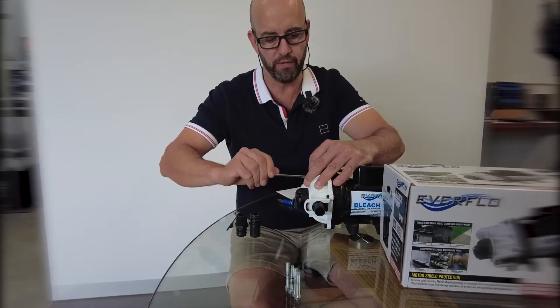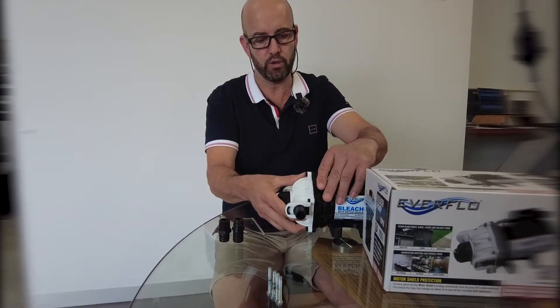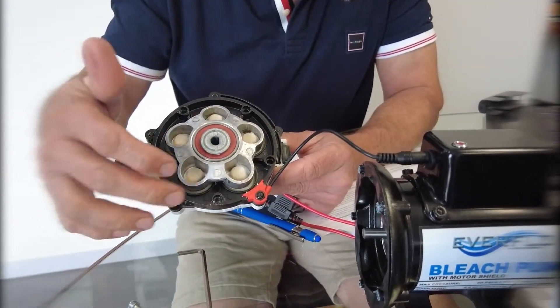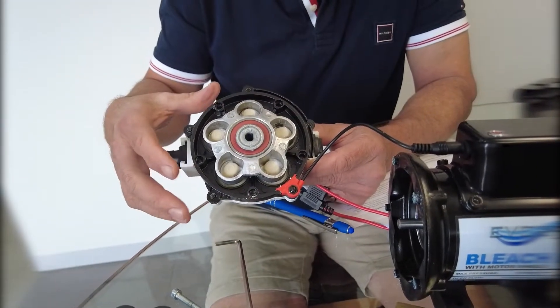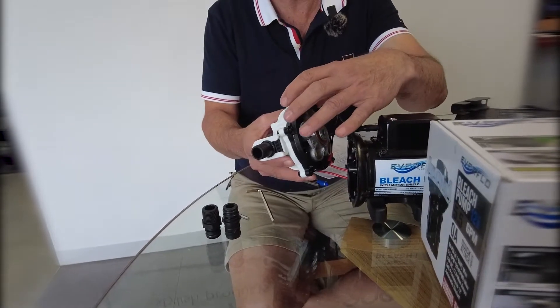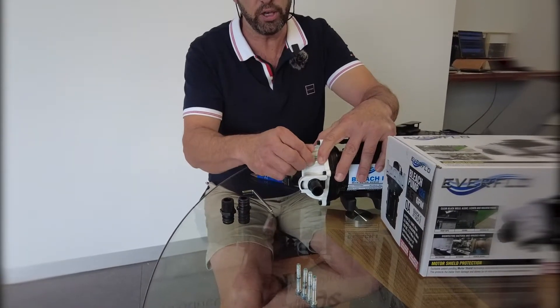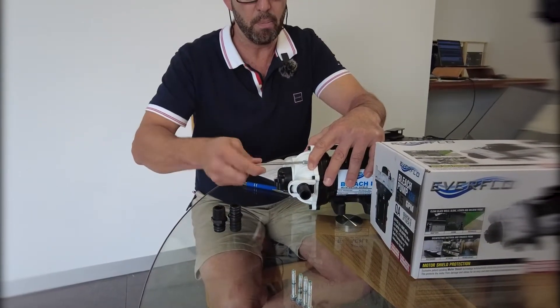The cartridges will be available shortly online as a separate component. Going forward, regular maintenance is just a change of the cartridge assembly. We can see the sensing switch, which will pick up current in relation to residual flow or leakage over those two probes to activate the fault light and disengage the pump. Undoing those five screws removes the cartridge — essentially the guts of the pump — for ongoing maintenance, then simply reinstall the new cartridge with a dedicated gasket between the two units and do the screws back up firmly.